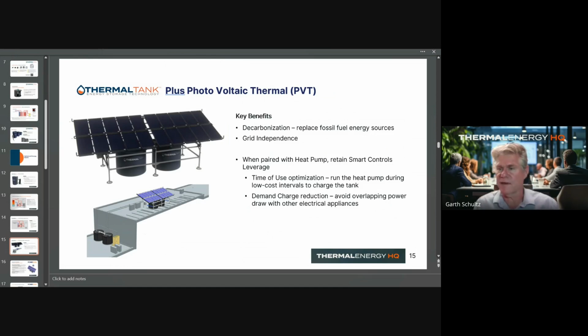Bolongo Bay Beach Resort had an older solar thermal system with multiple tanks that had cycled out or were no longer functional, and the hot water system was essentially unusable. Anyone in the four wings of the hotel, 45 rooms being serviced, woke up and whatever water was in there was what you showered with. The opportunity came to replace that system on the baseline, where you see two tanks and a heat pump installed, which we designed and specified. Then on the rooftop, to supplement and balance the electrical energy used by the heat pump, we put in our PVT system, which also supplies preheated water into that baseline system. So the two marry and work together.